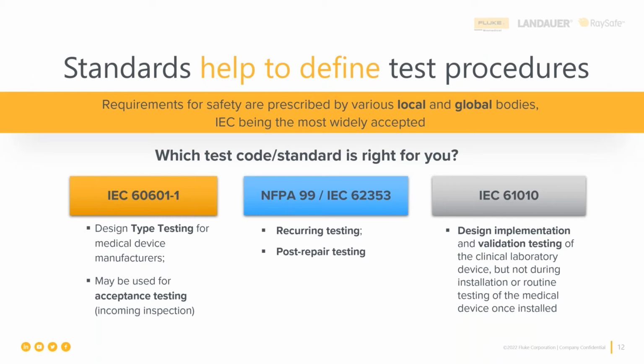60601-1. And this standard is written for the manufacturer of the medical device, to use in their design type testing, and they may also use it for their final assembly test in the factory. And that would be a very appropriate thing to do, because in the factory, the final assembly is the first time that all of the pieces, parts, and sub-assemblies have been pulled together into one complete medical device. And then it's definitely appropriate to run the test in accordance with the IEC 60601-1. They may be used for acceptance testing by hospitals and other facilities, but there's also a shorter test that can be done that should be sufficient.